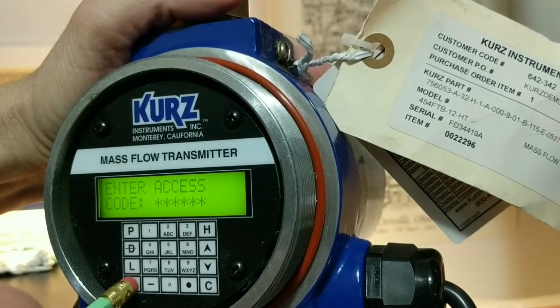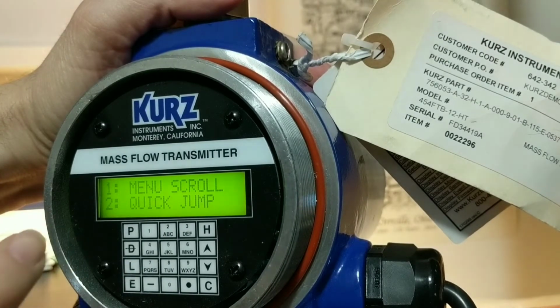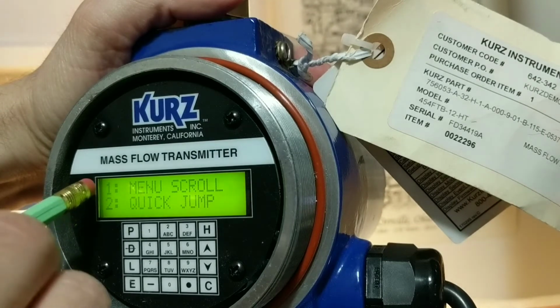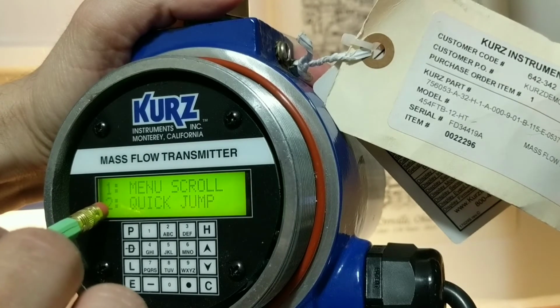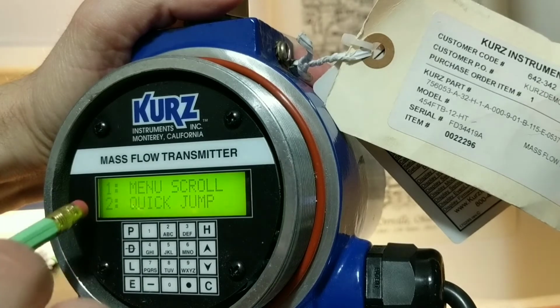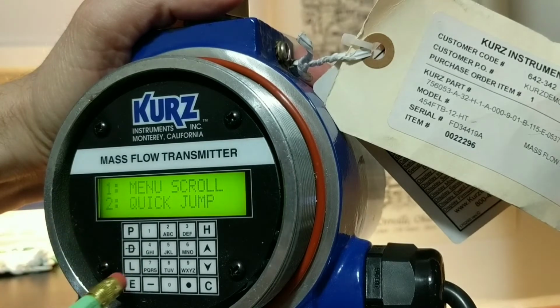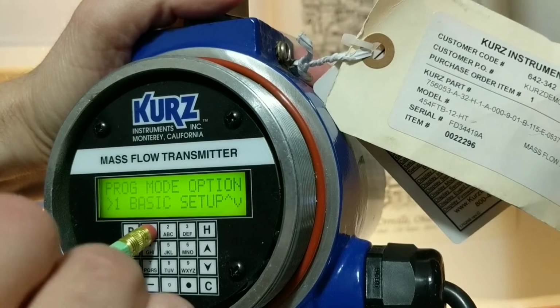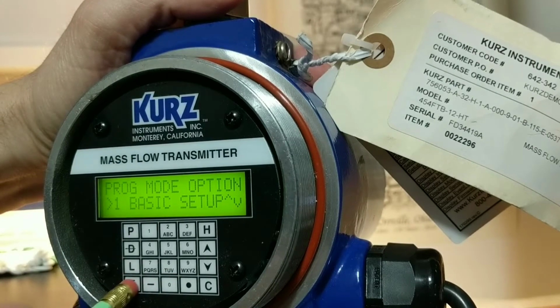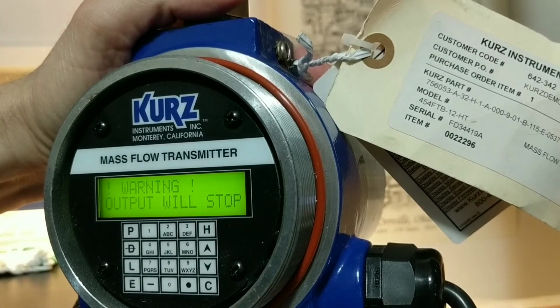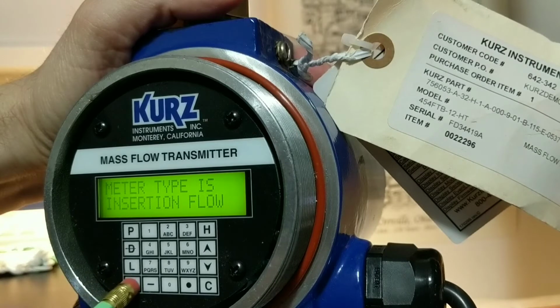65432, Enter. And now it's going to tell you you can do a quick jump if you know the number of the menu item, but we're going to go straight down through scrolling. So we'll just hit 1. We're going to go into the basic setup. Enter. It's telling you that the analog output is stopped. The meter is insertion flow. We already know that. And by hitting enter, we're just going to drop down through each of these items until we get to what we're looking for.